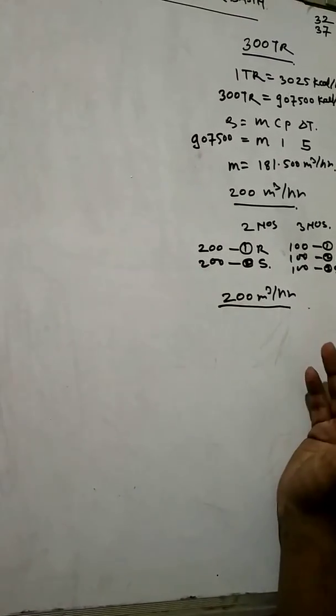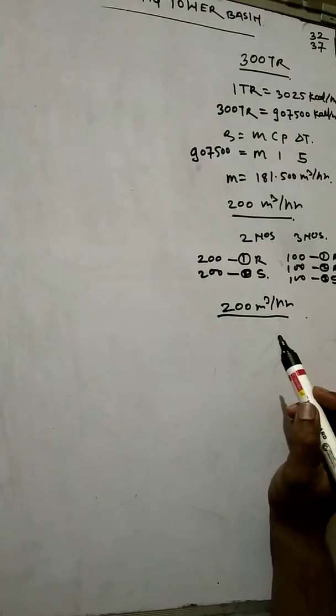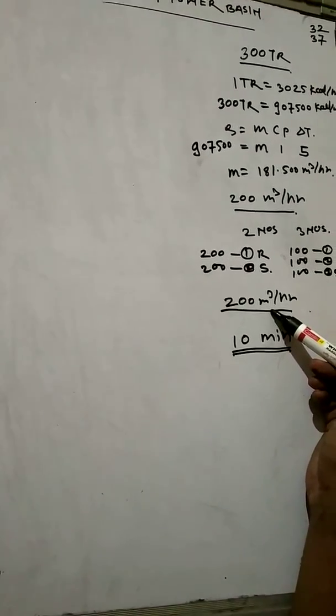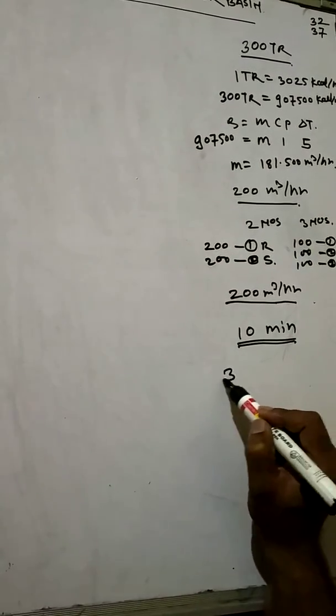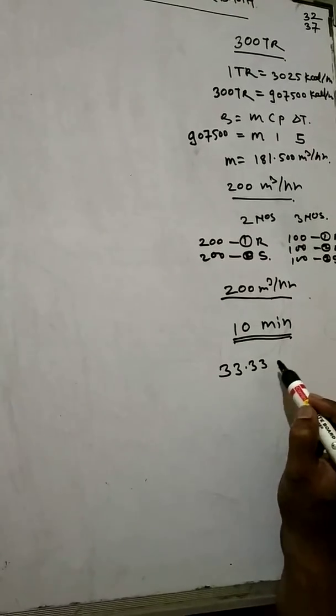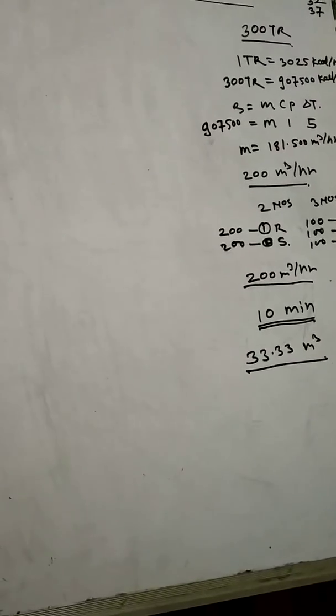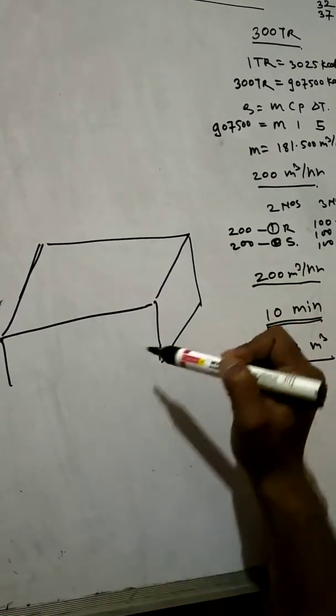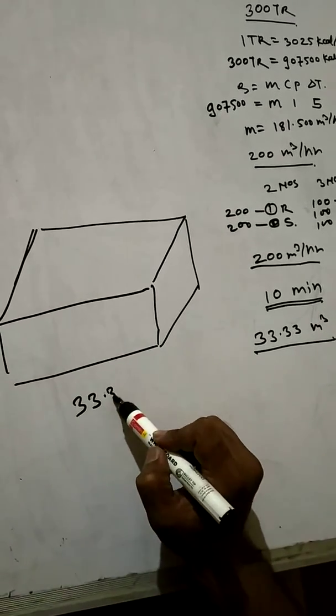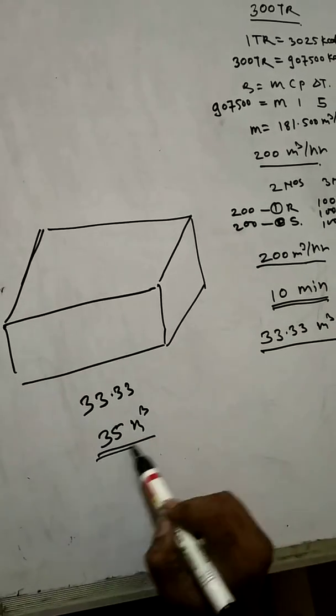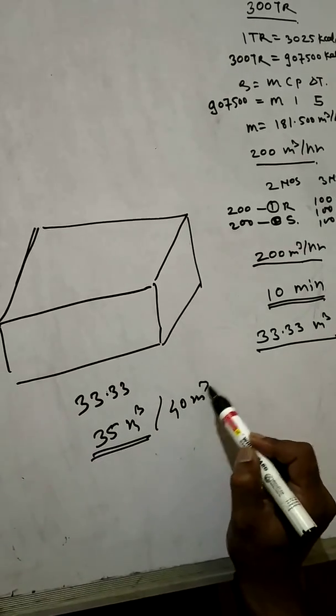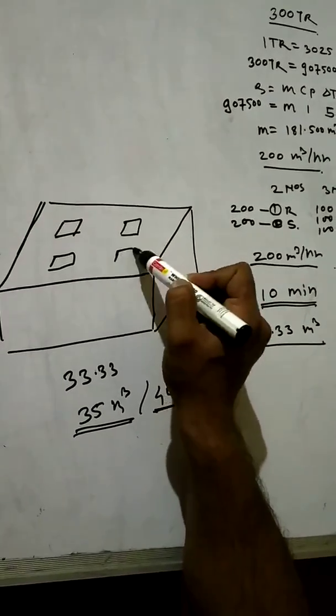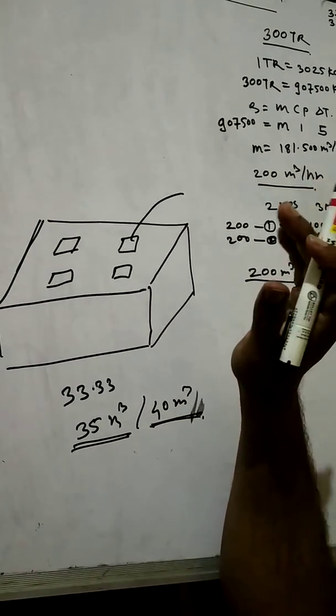With a pump capacity of 200 m³ per hour, what will be the basin size? The basin should provide 10 minutes of storage. That means 200 m³/hr ÷ 6 = 33.33 m³. So your cooling tower basin capacity will be 33.33 m³, or round up to 40 m³. The pedestal dimensions will depend on the cooling tower manufacturer's equipment specifications.